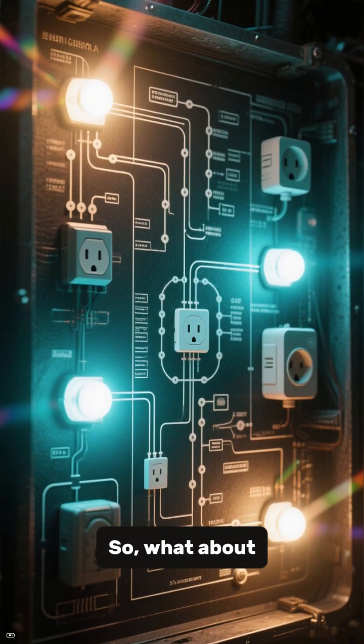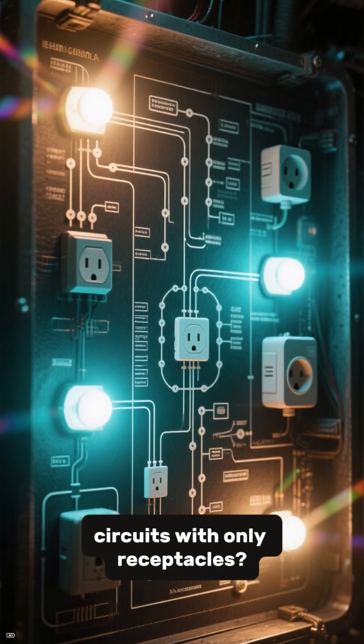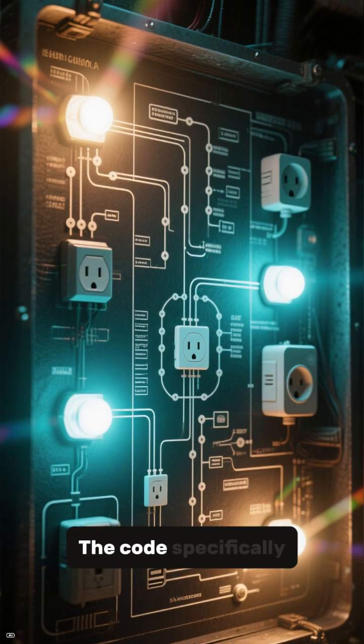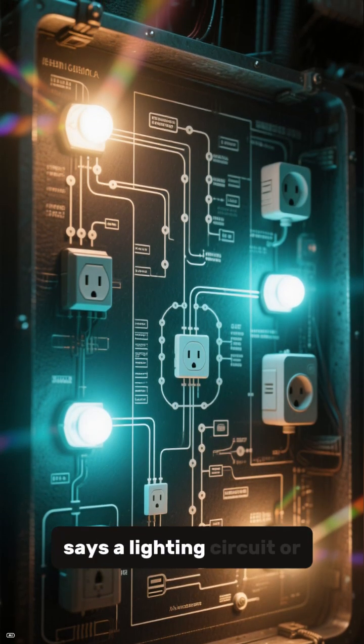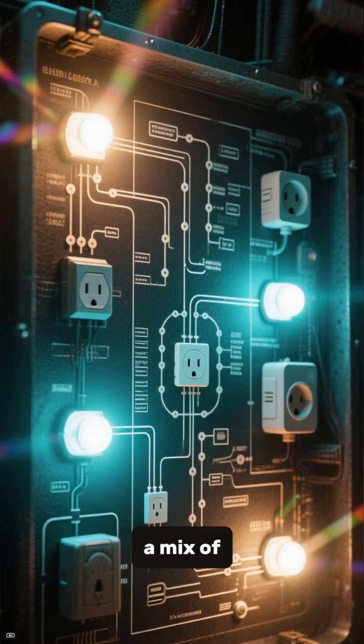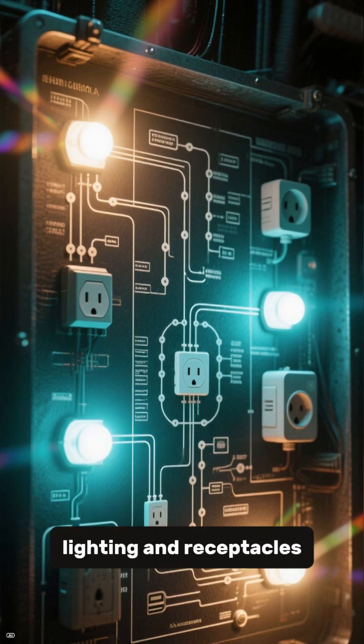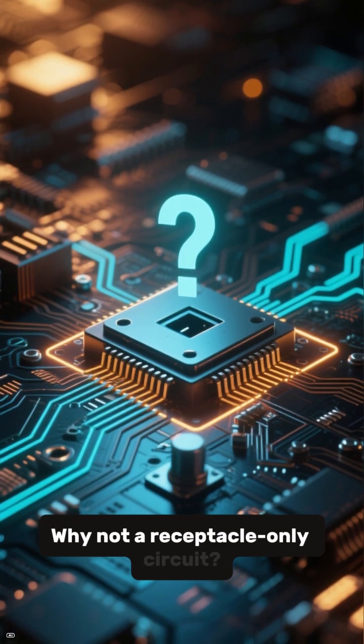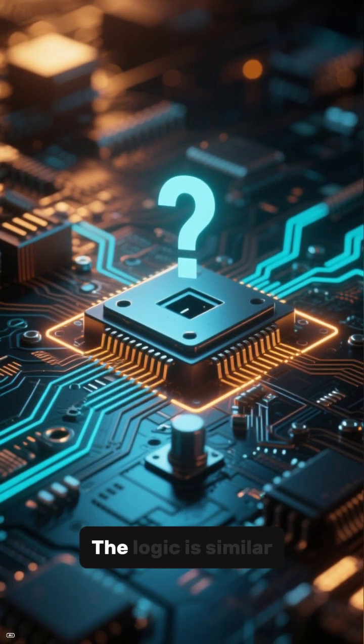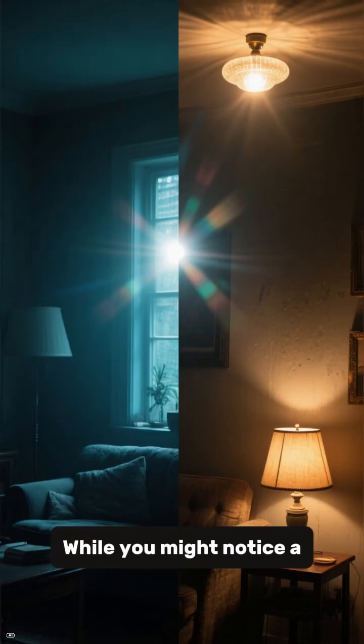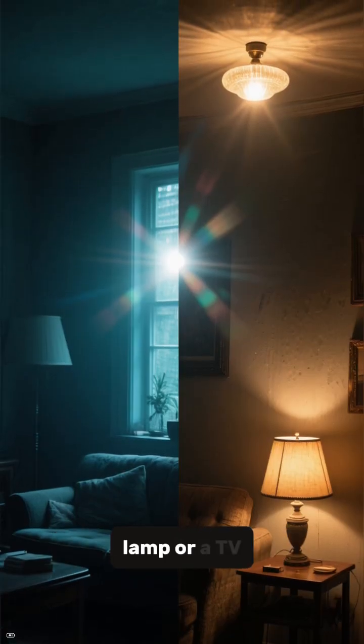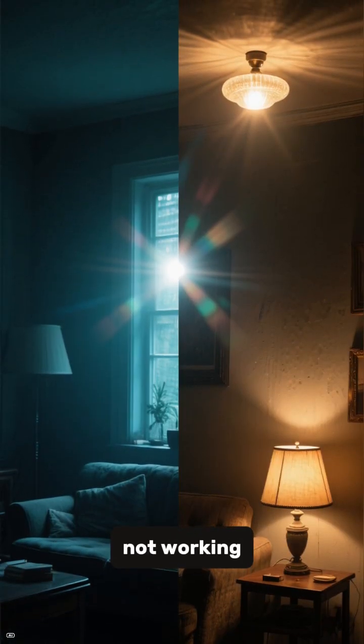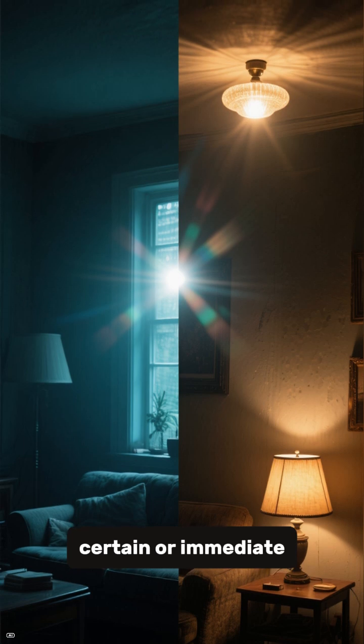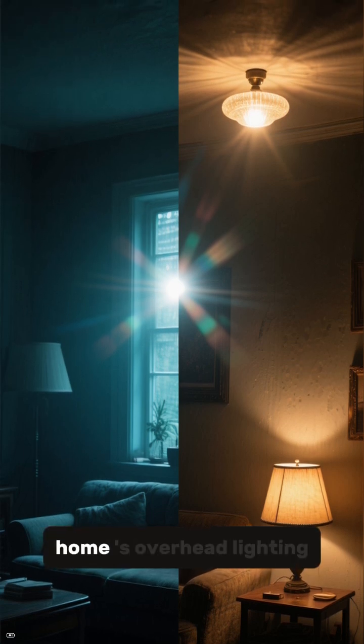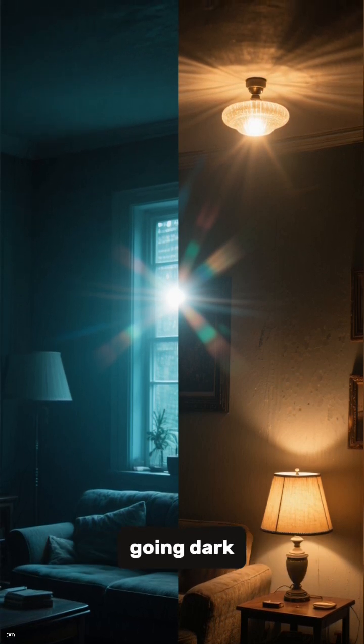So, what about circuits with only receptacles? The code specifically says a lighting circuit or a mix of lighting and receptacles. Why not a receptacle-only circuit? The logic is similar. While you might notice a lamp or a TV not working, it's not as certain or immediate as a whole section of your home's overhead lighting going dark.